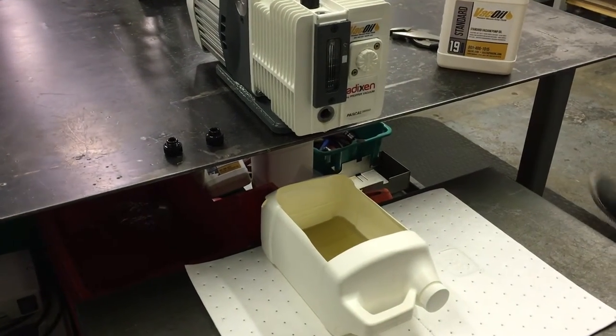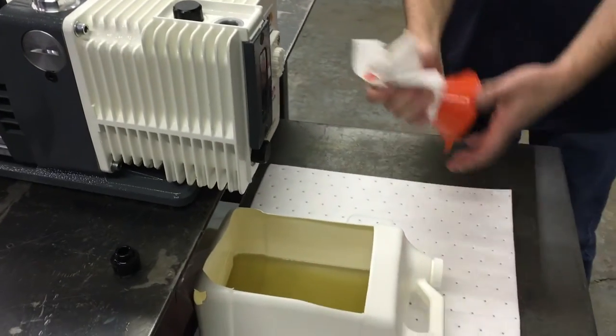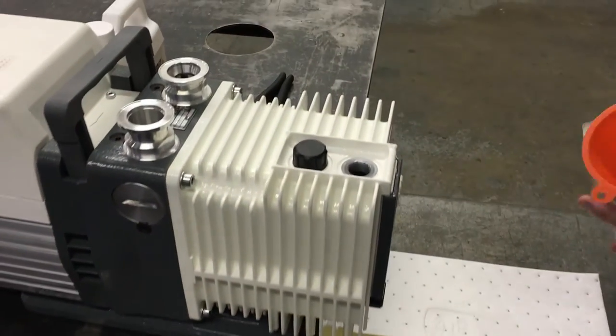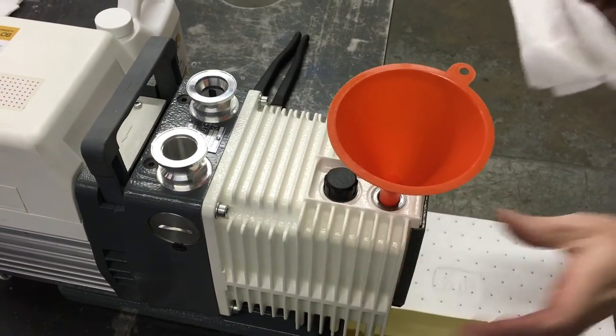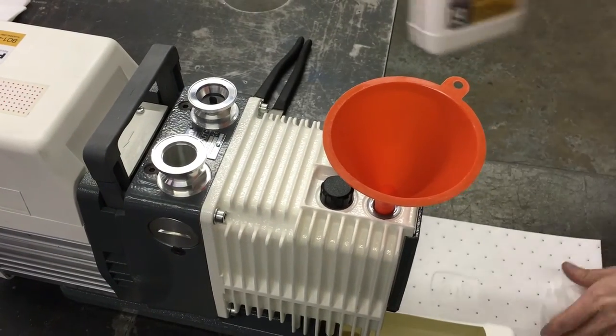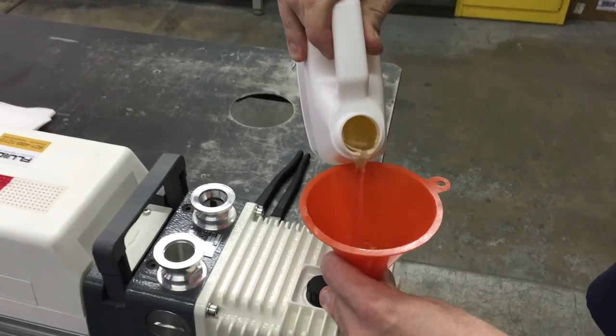Next, use a clean funnel to add new vacuum pump oil. Make sure to clean and dry the ports and plugs with a clean rag. Always use a high quality vacuum pump oil. I know this is obvious but replace the drain plug before you pour the oil back into the pump.